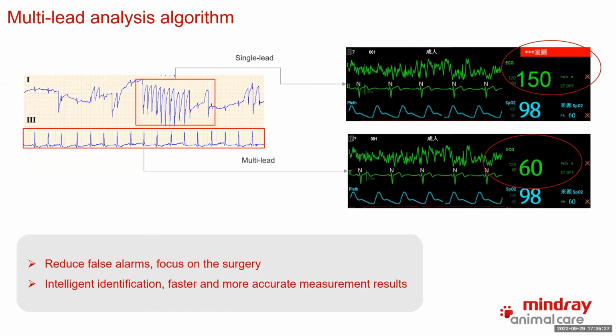So for us, we have the multi-lead analysis algorithm. If lead one right now is having some interference, and you're choosing it to do the ECG monitoring, you can see the ECG heart rate will be 150, and actually it's a false reading. But since we have the multi-lead algorithm, we can detect that on lead 3 right now the signal is good, with no interference. So we can do the calculation based on lead 3. And you can see the heart rate is 60, and it's a normal heart rate. So it can reduce the false alarms and also let the doctor focus on their surgery. It will also give you a fast and more accurate measurement result for the ECG, for the heart rate, and also for the arrhythmia analysis.